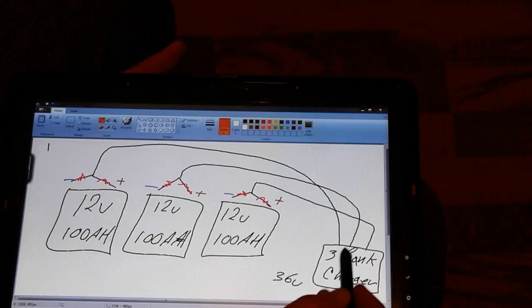We talked earlier about not hooking the negatives together in a series connection. Here's our series connections going down to create our 36 volts. Imagine if internally that charger, one of the isolated grounds actually connects to another because of a problem in the charger. Without a fuse there, you basically get current flow all the way back into the charger and out to the port where the isolation has gone away, back out on that ground side, and you've created a dead short. Those wires will get hot.